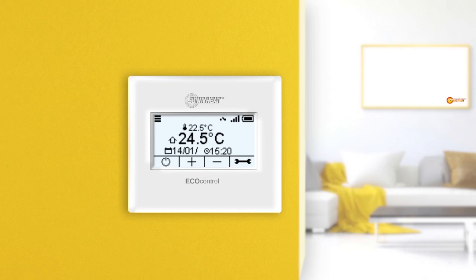If the switch-off bypass is activated, one of the time periods has come and the outside temperature is equal to or lower than 12.5 degrees Celsius, the switch-off bypass symbol appears on the main display. The set point temperature is raised by the specified temperature in the Temperature Increase menu. In this example, by 2.5 degrees Celsius. The set point temperature is therefore 22.5 degrees Celsius.